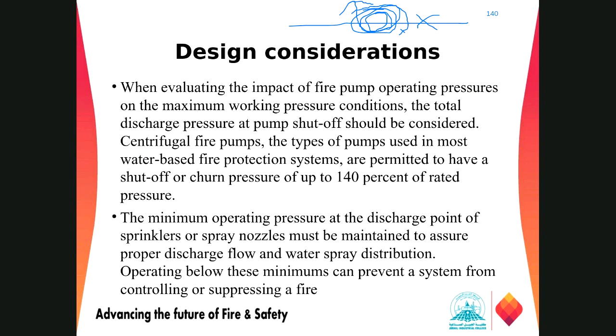Just what you mean, for example, the maximum pressure, which is the zero flow or shutoff pressure. If it is exceeding the 175 psi, then all our system and piping and everything should be rated for a higher pressure. Exactly. We don't need more than 175 psi in our fire protection system. We have to keep that in mind.